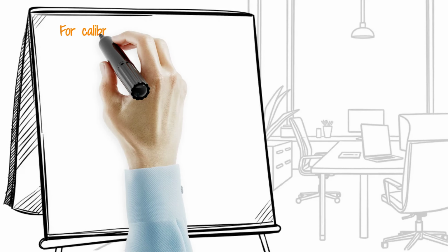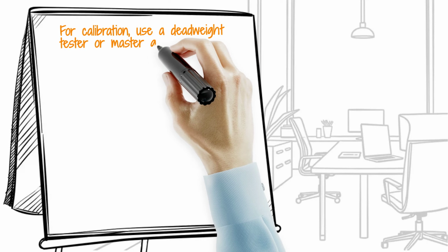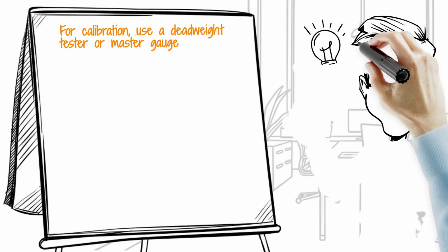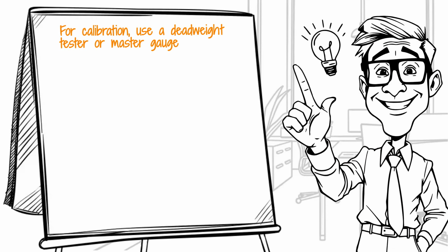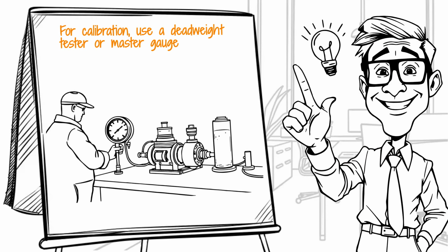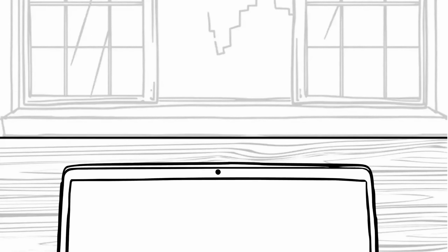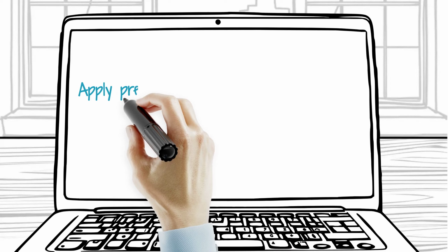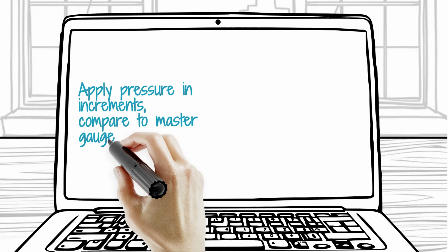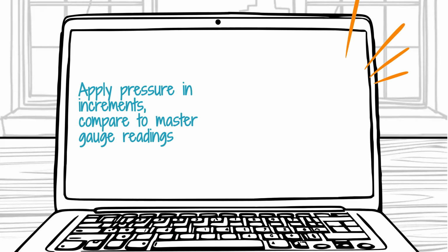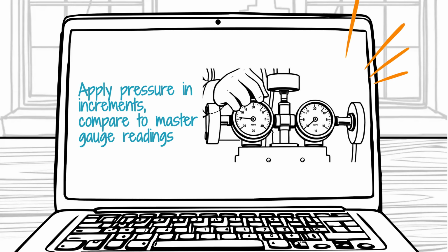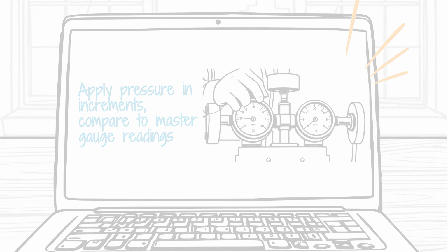To perform a proper calibration, you will need a deadweight tester or a high-quality master comparison gauge. Connect the gauge to the test manifold and ensure there are no air bubbles trapped in the oil line. Start the calibration by applying pressure in increments of 20% across the full scale of the gauge. At each step, compare the reading on the gauge under test with the master gauge or the weights on the tester.